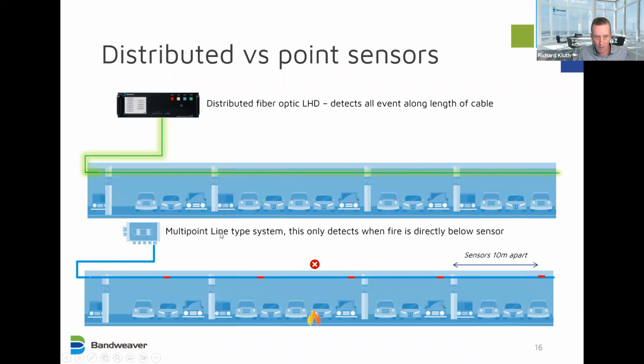If we look at a line type point system where you have points spaced perhaps every 10 meters apart, if the fire is here, it's between sensors, and so it would have a much slower response. The fire would have to build much more before the heat develops to here. Similarly, if it's here, again, a delayed response. Sometimes it will be directly below the point, but when you're doing system design and system commissioning, you have to take the worst case scenarios. And so it's very important, the continuous coverage.